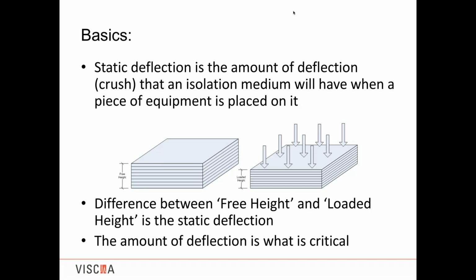Here's a very simple illustration of what I'm talking about with static deflection. I have any medium, I'm calling it a medium just to be generic. It can be an elastomer, a spring, a block of wood, an airbag. It's just a medium that's placed under the equipment. It has a free height, static height, 1 inch, 2 inch, 3 inches, whatever it may be. You place a piece of equipment, a load on top of it, and it's going to deflect. If it doesn't deflect and it's rigid, you don't have isolation. You need deflection. So the difference between the two heights, the free height without any load and the height with the load, is considered the static deflection.